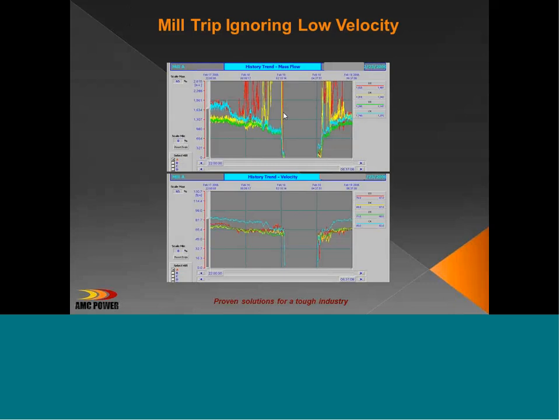And some plants allow us to dial in, so we remotely dialed in, and we could see that 2 pipes were plugging over several hours, the red and the yellow. And eventually, as they plug, there's nowhere else for the coal to go. It bogs down in the mill, plugs, and we tripped the mill. But what's more telling is the velocity screen. Throughout the course of that night, and this can be a classic case of wet coal, the velocity of the coal particles is slowing down. And eventually we get to where those particles will no longer move and they start to pile up, as we see in the red and the yellow pipe.